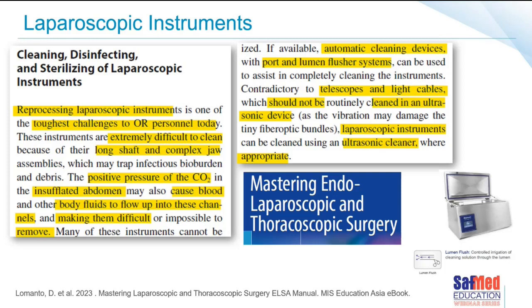They've got extremely difficult to clean long shafts. They've got complex, small, tiny jaws on them often that can trap a hell of a lot of infectious bioburden and debris. Then you have to think about the fact that the positive pressure of the CO2 in the insufflated abdomen can also cause blood and other body fluids to flow up the channels, making it quite difficult to remove. So very difficult to manage these instruments.